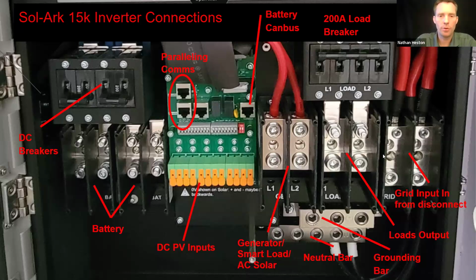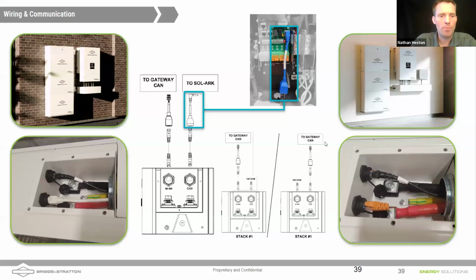Nice, and thank you for highlighting that. So on the top of the battery, the connections, the only real wiring you have to do on this stackable battery is really these home runs. The power output out of the battery controller. There's a grounding connection that's here that's not always required. It depends on your jurisdiction whether or not they want you to ground the battery, but then the communications cabling.